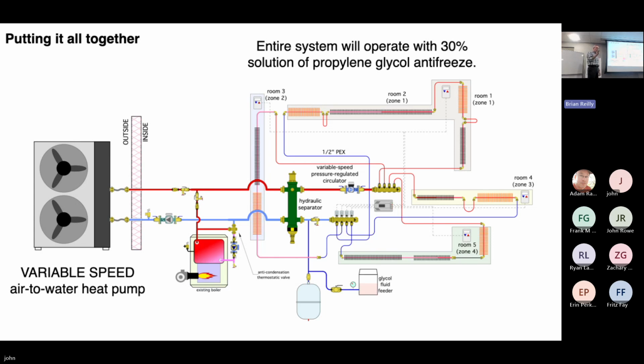And you could use separate heat pumps, or one could take priority over the other. The heat pump could switch back and forth, but it's only capable of so many BTUs per hour. So depending on what those loads are, you'd have to decide, do I want a single heat pump and just toggle it between the 2 tanks with an electric valve system? Or do I want a separate heat pump for heating? You might put a 5-ton heat pump in for heating and a 3-ton heat pump in for cooling, depending on what your loads are. That's one approach.